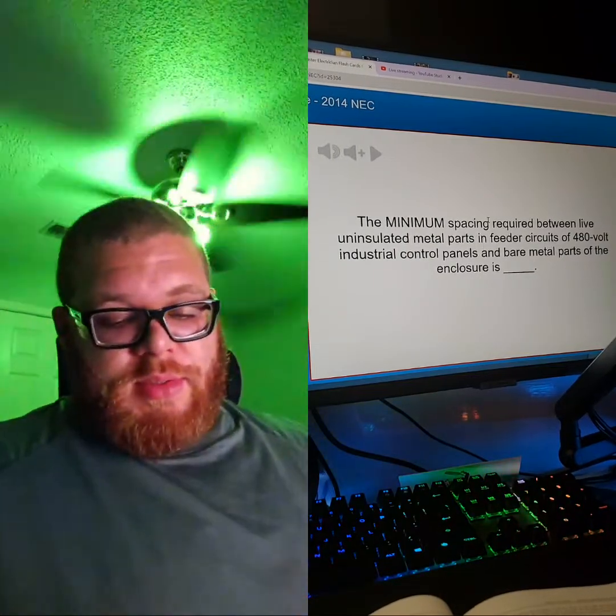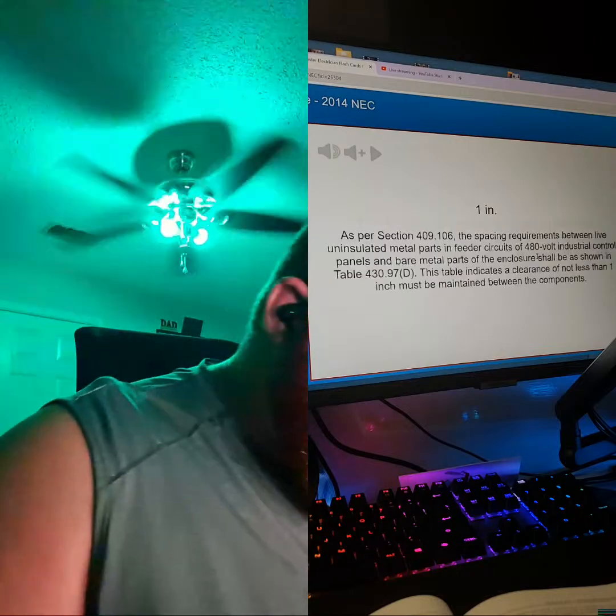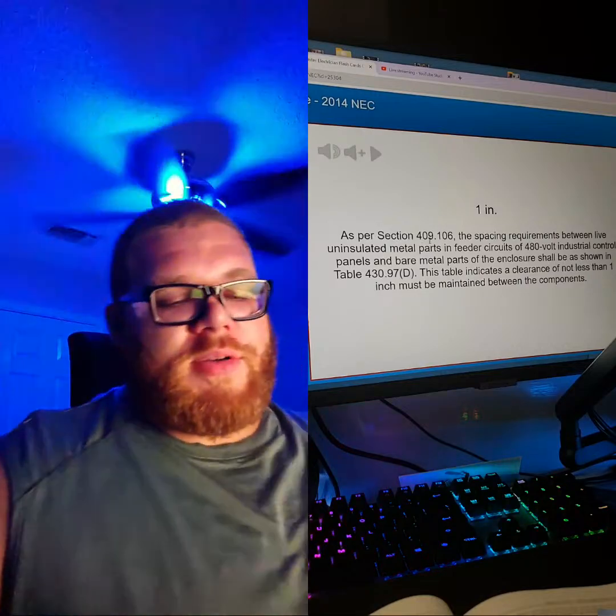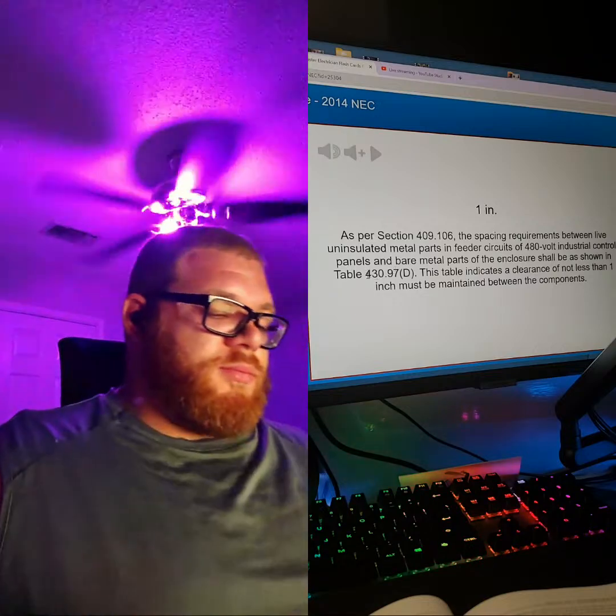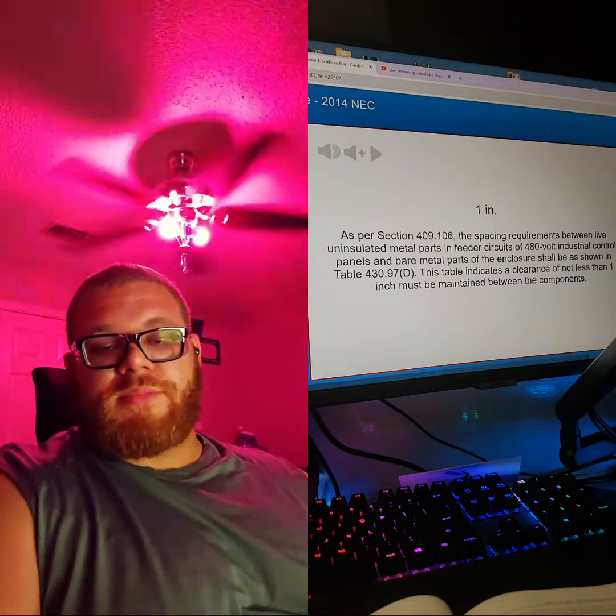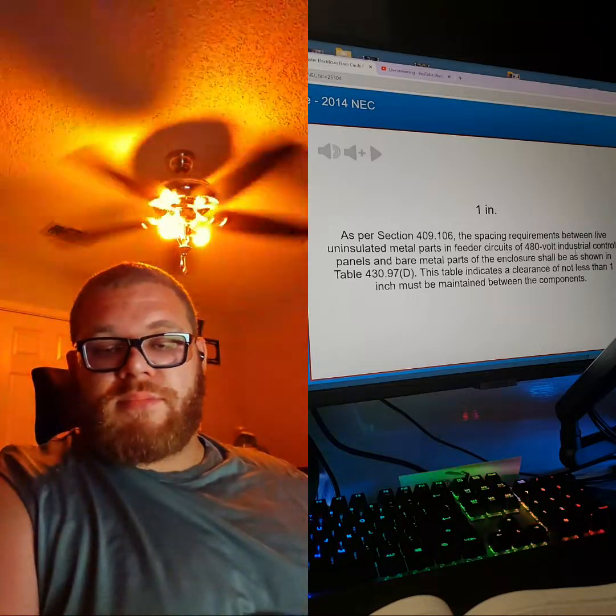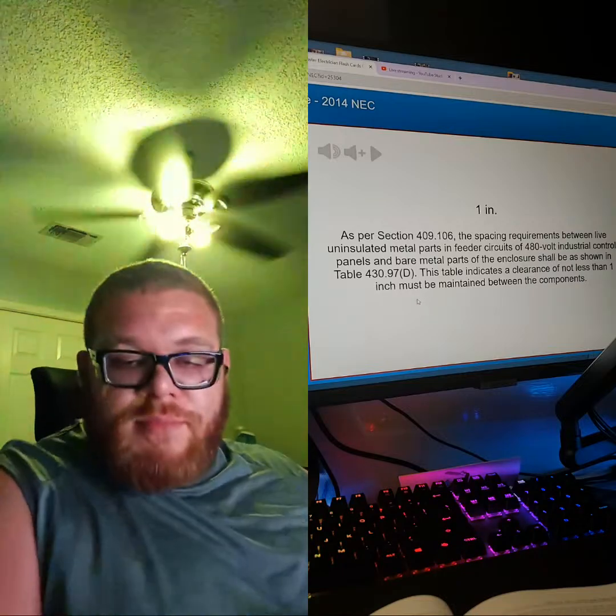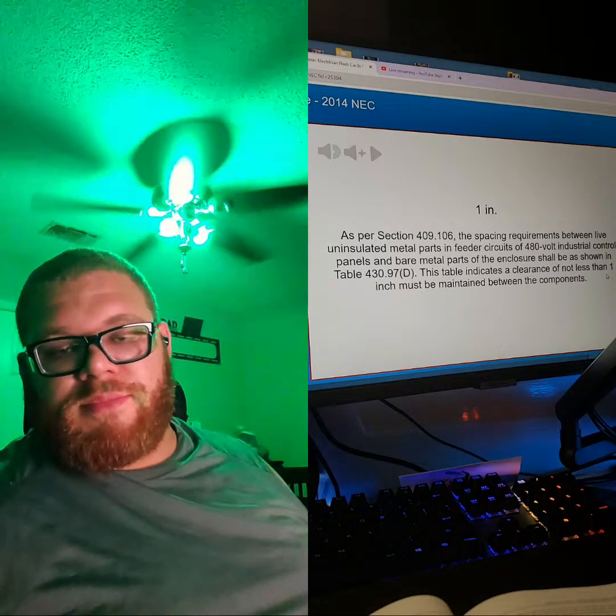430.97(D). Look at 408.56. I found it by going into the index. I searched live parts, and then I also searched enclosure, and it's in 409 too. You're also right. So you found it both ways. If you find 409.106, spacing requirements between live uninsulated metal parts and feeder circuits, 480 volts, industrial control panels. And then you've also got 430.97(D), which is where you found it. So we both found it in different spots. That's cool.